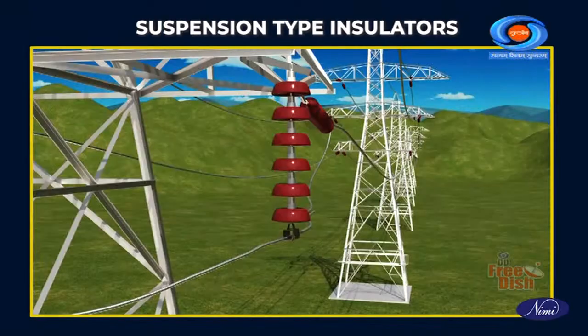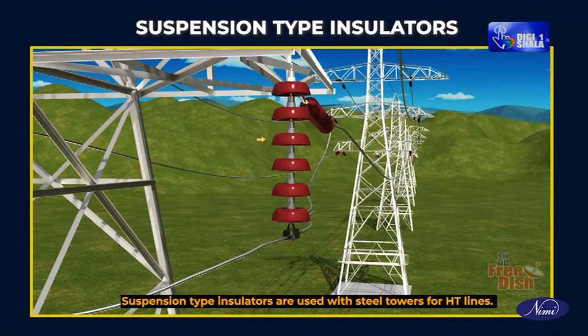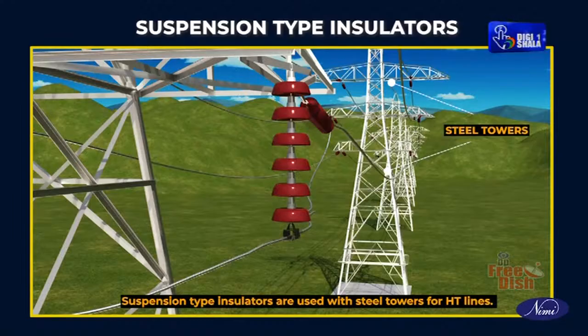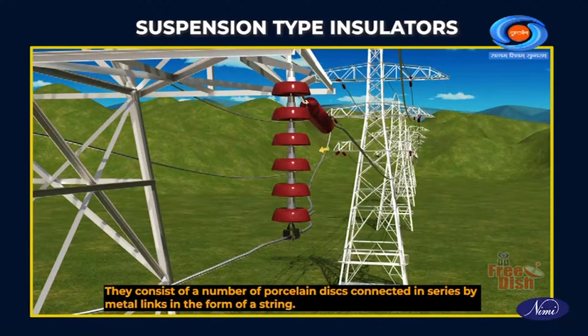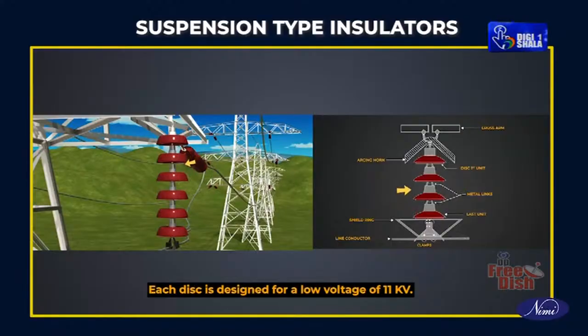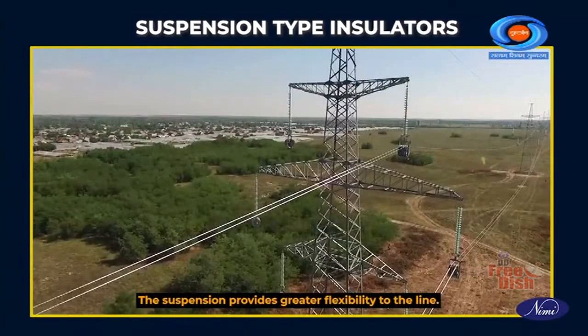Suspension type insulators. Suspension type insulators are used with steel towers for HT lines. They consist of a number of porcelain discs connected in series by metal links in the form of a string. Each disc is designed for a low voltage of 11 kilovolts. The suspension provides greater flexibility to the line.